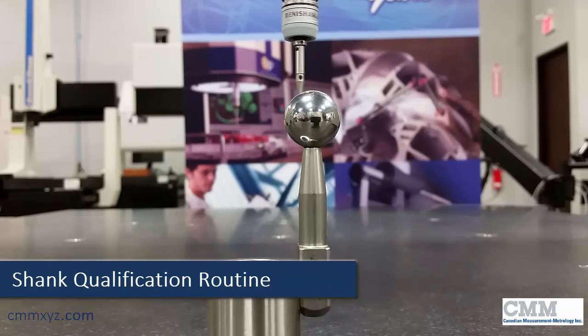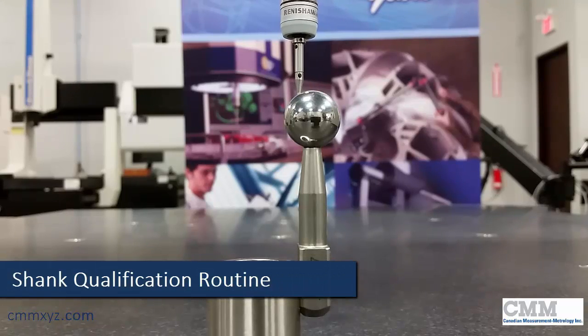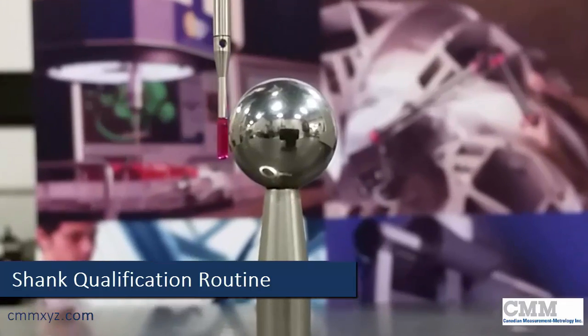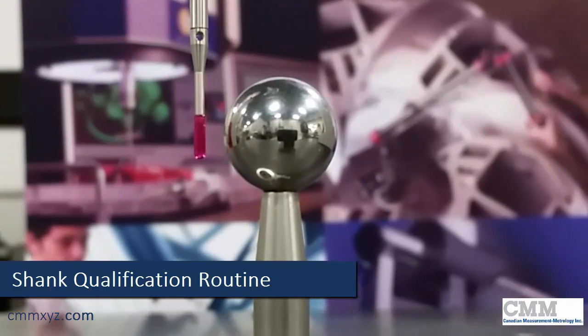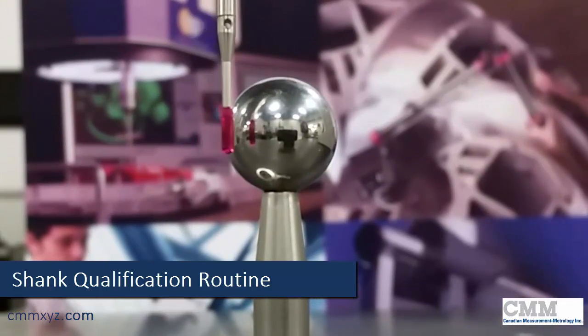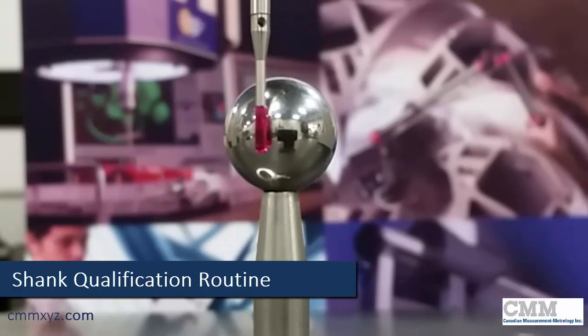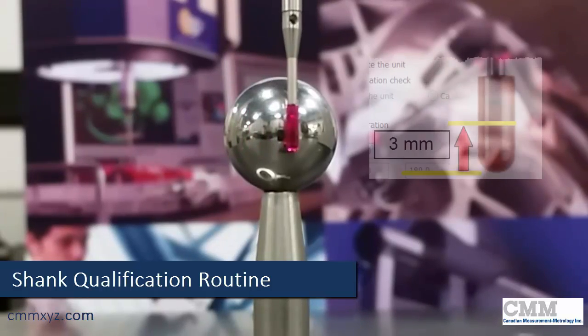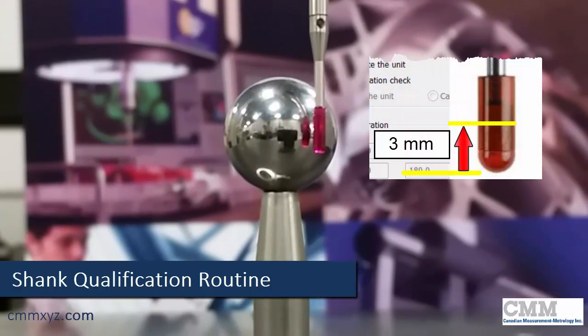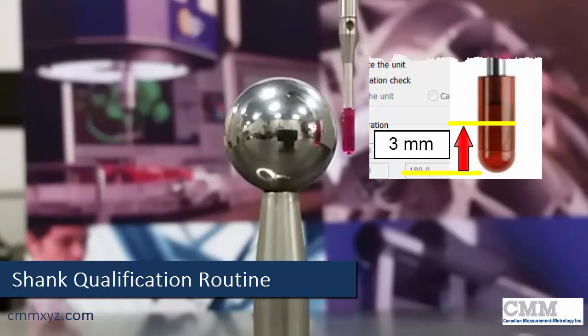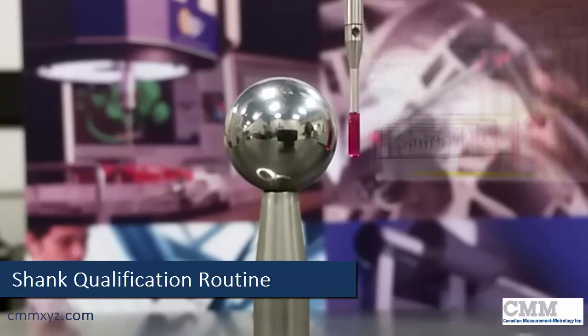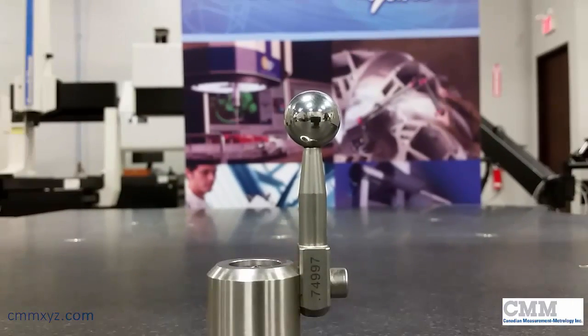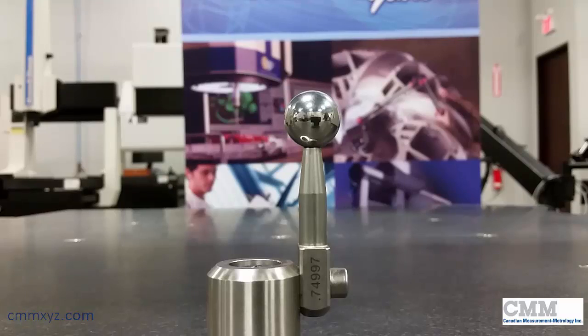Here's our shank qualification at that three millimeter offset. You can see there's a good view of it there, just slightly below the equator. It's calibrating at that tangent point, three millimeter distance up from the bottom of the tip. There we go, we're done.